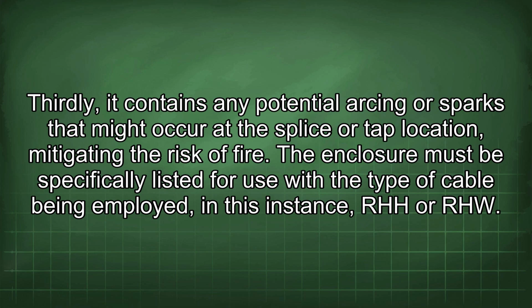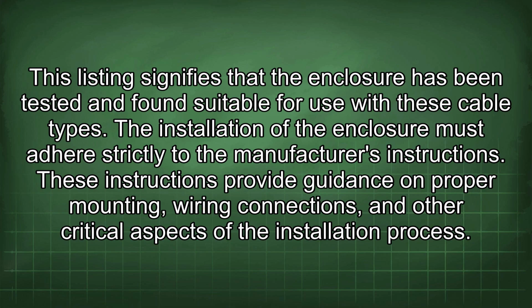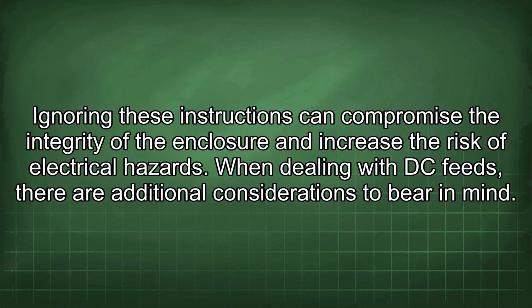of fire. The enclosure must be specifically listed for use with the type of cable being employed, in this instance, RHH or RHW. This listing signifies that the enclosure has been tested and found suitable for use with these cable types. The installation of the enclosure must adhere strictly to the manufacturer's instructions. These instructions provide guidance on proper mounting, wiring connections, and other critical aspects of the installation process. Ignoring these instructions can compromise the integrity of the enclosure and increase the risk of electrical hazards.